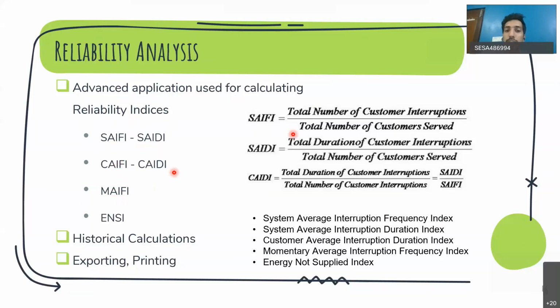I've given a formula as an example. SAIFI gives you, in general, the number of interruptions that occurred on a particular feeder. The formula is total number of customer interruptions divided by total number of customers. If you cancel the number of customers, explained crudely, the SAIFI value will be approximately the number of interruptions occurred on that network.